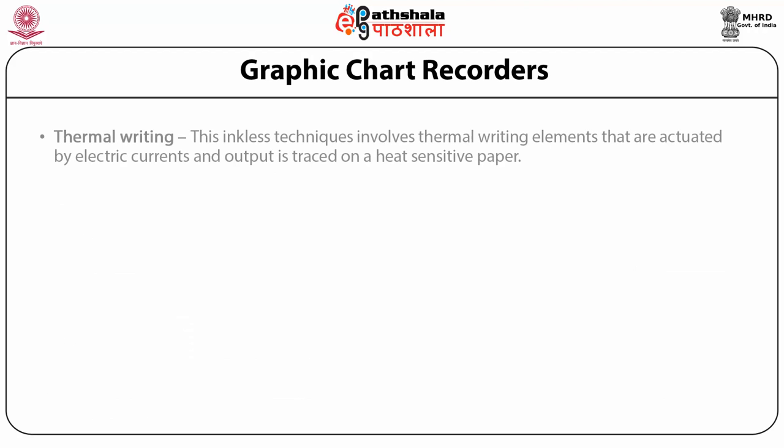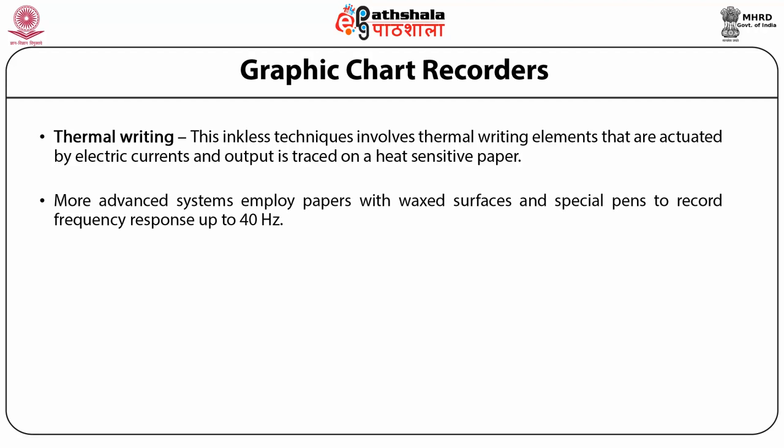C. Thermal writing: This inkless technique involves thermal writing elements actuated by electric currents, and the output trace is recorded on heat-sensitive paper. This method is most reliable and produces higher contrast traces. More advanced systems employ papers with wax surfaces and special pens to record frequency response up to 40 Hz.